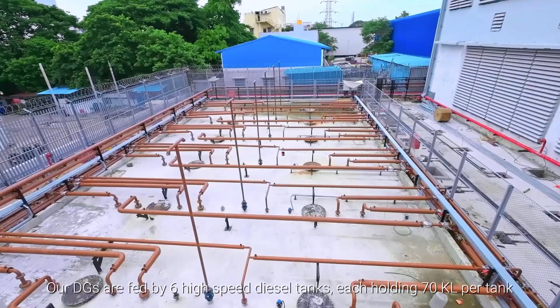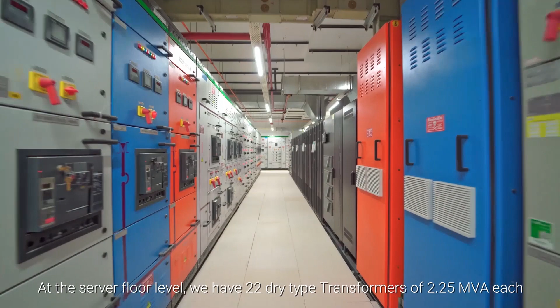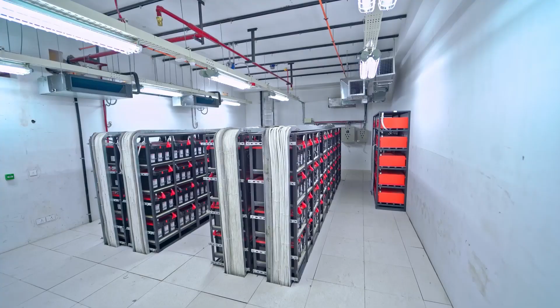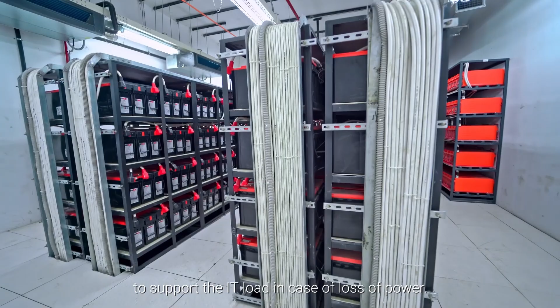Our DGs are fed by 6 high-speed diesel tanks, each holding 70 KL per tank. These can keep the entire facility running for 48 hours on full load. At server floor level, we have 22 dry type transformers of 2.25 MVA each, which step down from 11 kV to 440 volts in block redundant mode. Also, we have additional UPS battery backup of 10 minutes to support the IT load in case of loss of power.